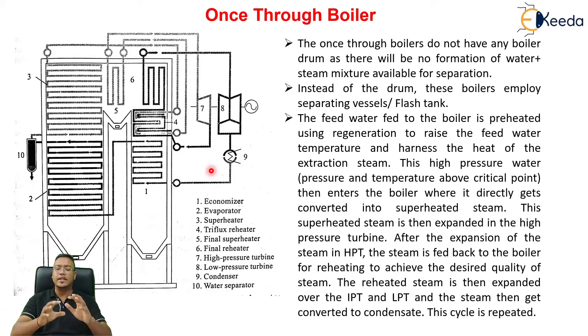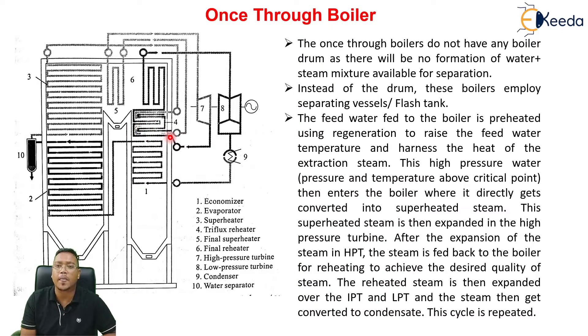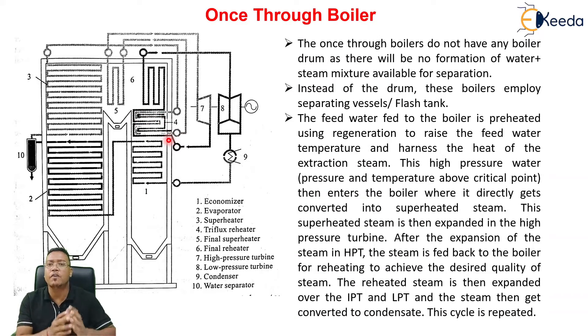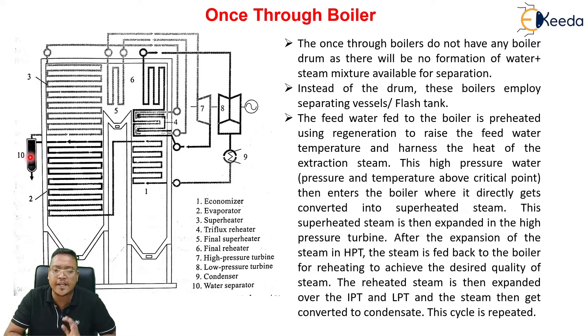This is a Sulzer-make boiler. In this case, there is a tri-flux reheater — we are using two reheaters. This reheater is taking heat from two sources: one is from the flue gas, and the second is from the steam going into the superheater. So this reheater takes heat from both the flue gas and the superheated steam, which is why it is called the tri-flux reheater. In this case, there is a flash tank and there is no steam drum.